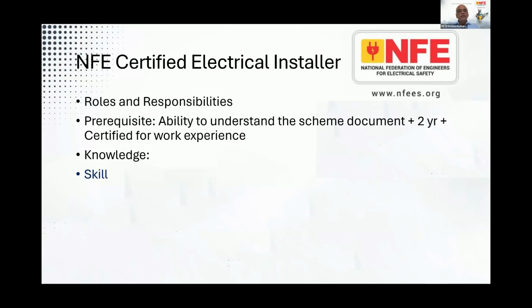For knowledge, they should know that conductors and terminals should be identified according to IEC 60445. Equipment should be installed such that heat dissipation is not hampered. Any equipment likely to cause high temperatures or electrical arcs shall be placed or guarded so as to minimize the risk of ignition. The exposed parts of electrical equipment are to be taken care of, and suitable warning signs provided. In case of alterations to an existing installation, you should determine that the existing cables can carry the load, or else provide for changing the incoming cables also. And then look at the earthing and bonding arrangements so that the protective measures applied for safety are adequate for the new installation or alteration.